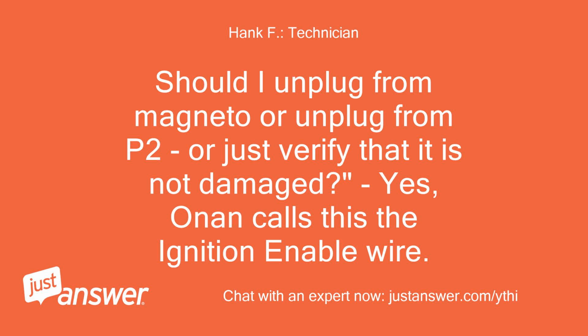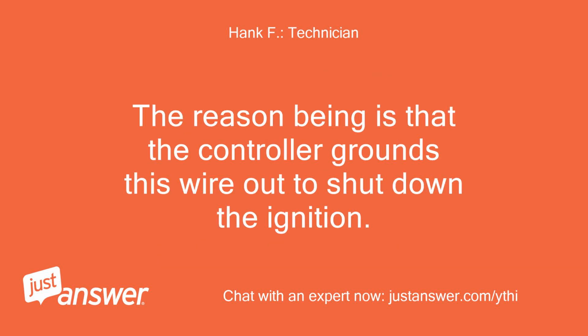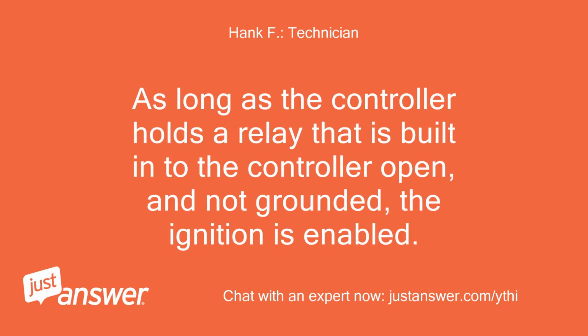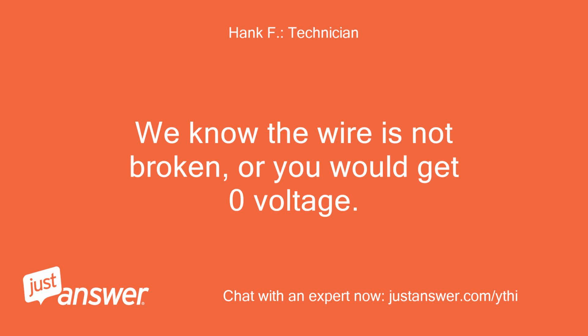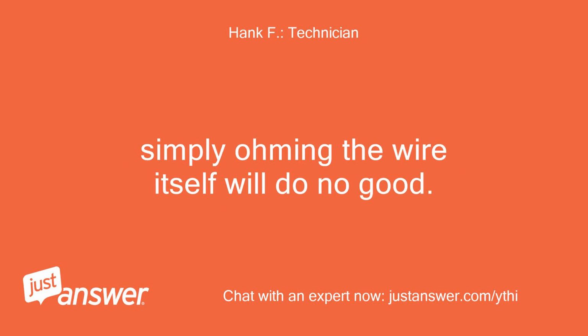Yes, Onan calls this the ignition enable wire. The reason being is that the controller grounds this wire out to shut down the ignition. As long as the controller holds a relay that is built into the controller open, and not grounded, the ignition is enabled. We know the wire is not broken, or you would get 0 voltage. Simply ohming the wire itself will do no good.